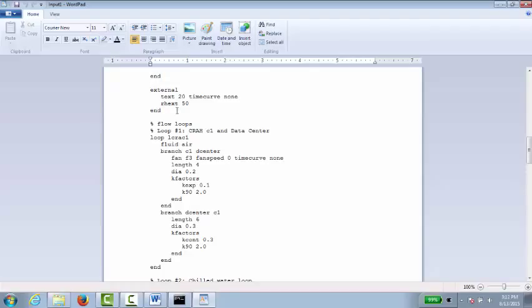Here we're specifying the T external and RH external, a temperature of 20 degrees C and a relative humidity of 50%. VTAS has the ability to grab data for specific locations and allow you to even model transiently how this data center would behave under the changing conditions of a given location. We have climate data from over 1,000 locations from the National Institute of Standards and Technology, and the data we have is hourly data taken over a typical year. This data includes the temperature and relative humidity.